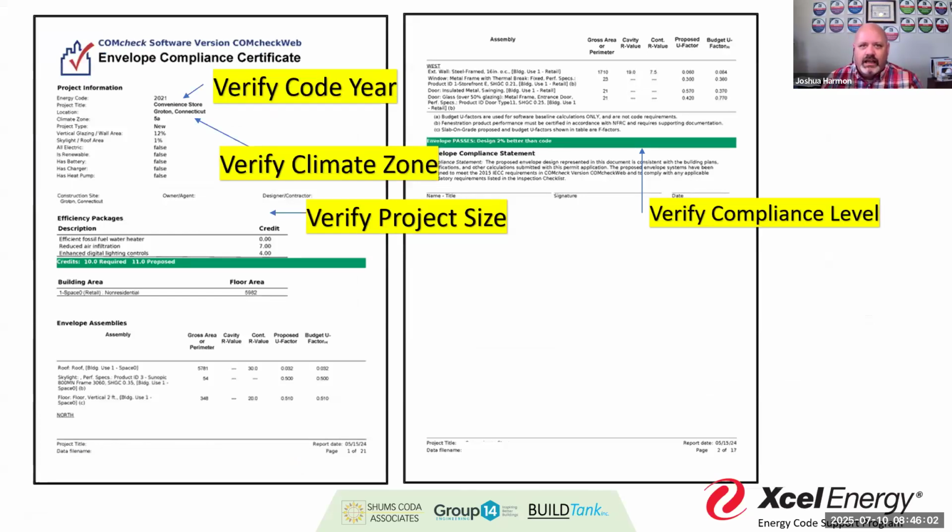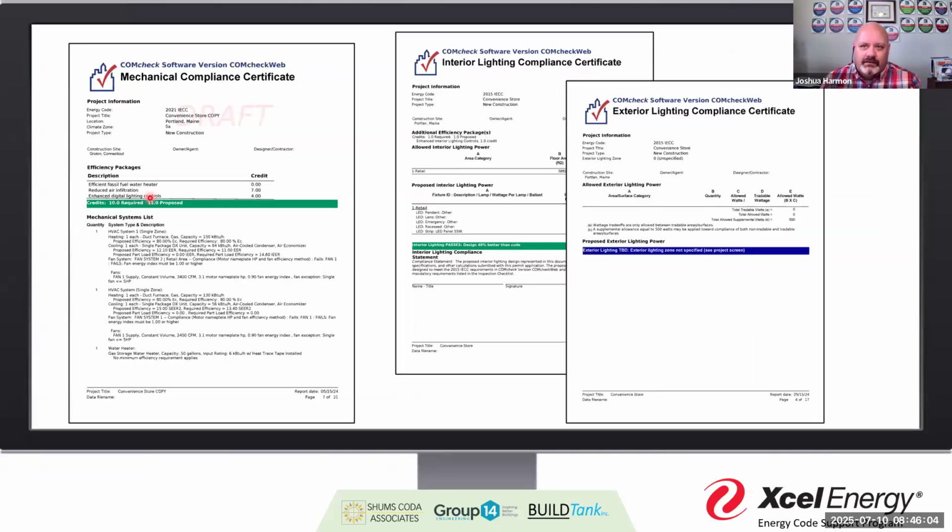But if we're looking at it from a perspective of the information input for the interior and exterior lighting or the mechanical systems, again, that is not coming from a database in the ComCheck. Someone is inputting those values. I was looking at one yesterday, not a huge deal. Their exterior lighting plan, they listed all the exterior lighting except for one particular type of fixture.